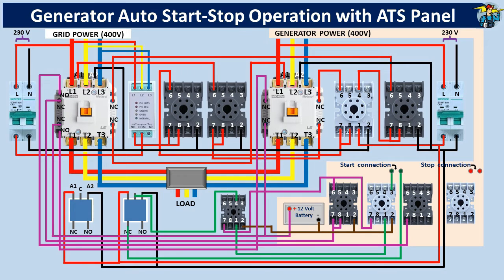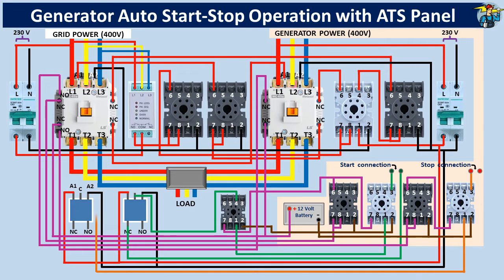Port number 7 should be connected to common port number 8. The negative end of the battery should be connected to port number 2 on the timer. Connect port number 6 of the generator stop timer to port number 7 of the generator stop relay. Connect the negative end of the battery to port number 2 of the relay. The stop connection points of the generator, where the stop push button or stop key is connected, will be connected through 2 relays — through the normally open contact points 1 and 3 of the stop relay, and through the common terminal and normally open terminal of the SPDT relay for generator stop control.